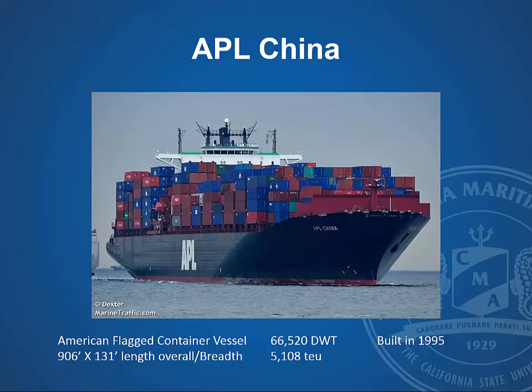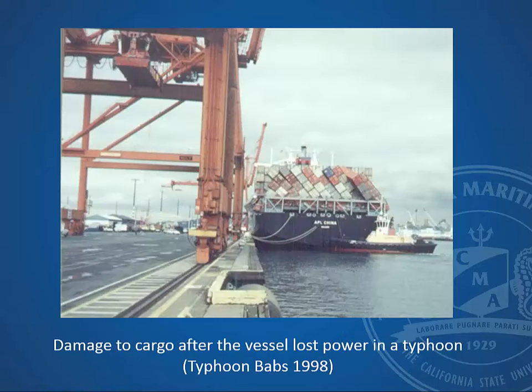Now I'm bringing up the APL China. The APL China is a container ship, 5,000 TEU, built in 1995, that is in the American flag. In 1998, while in a typhoon, the plant ended up blacking out. Now, the problem with this is that water on the main deck was actually able to hit the louvers that we talked about on their emergency generator, go into the emergency generator space, and was not draining fast enough and got up high enough to knock out the 24 volt distribution bus.